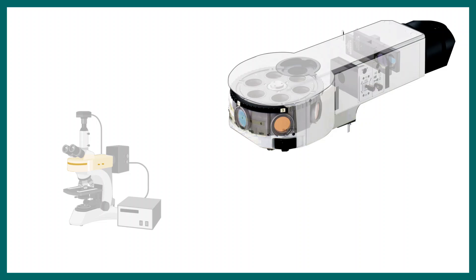Actually, a microscope has an array of filter cubes. That means there are more than one filter cube present in a filter wheel kind of setup in the microscope. By rotating this filter wheel, we can select our wavelength of illumination of the specimen. We can illuminate GFP, RFP or whatever fluorescent molecule we like. Filter cubes are really an essential part of a fluorescence microscope.